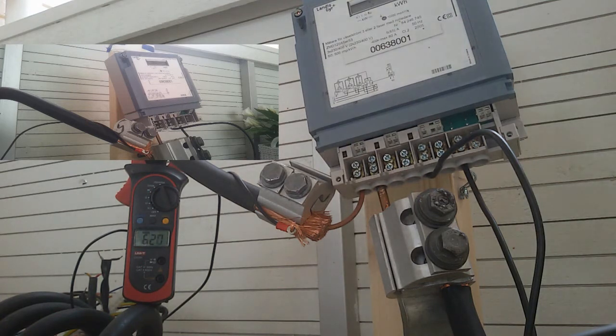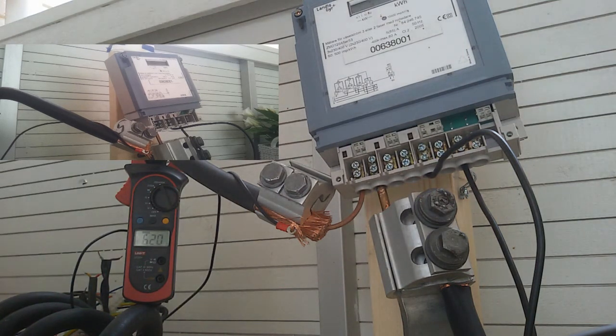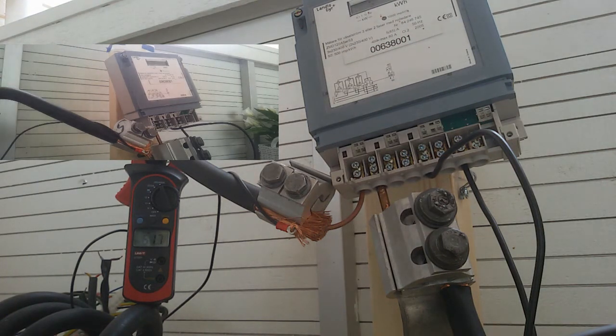So yes, the electric meter didn't turn on. This is rated for 80 amps, and now the current is 6.10 amps, 6.20 amps. I wanted the electric meter to turn on. It stands on 2 or 3 phases, so that's the problem. It's made for 2 phases, meaning it needs 400 volts to operate, which is why it didn't turn on.